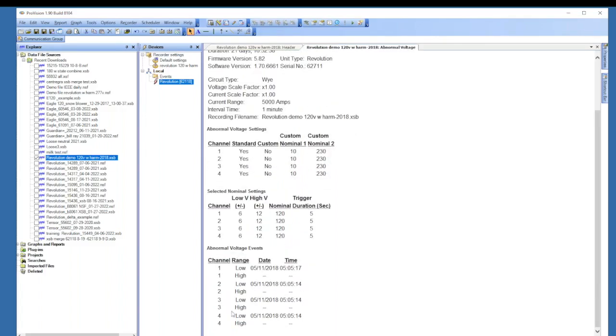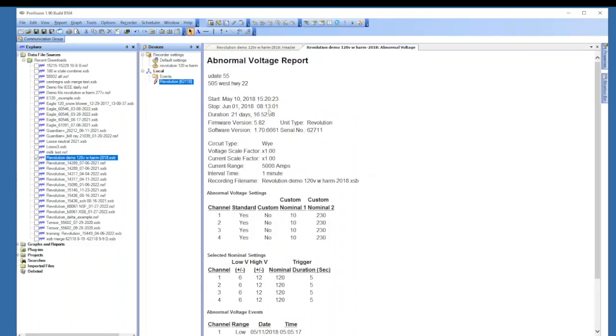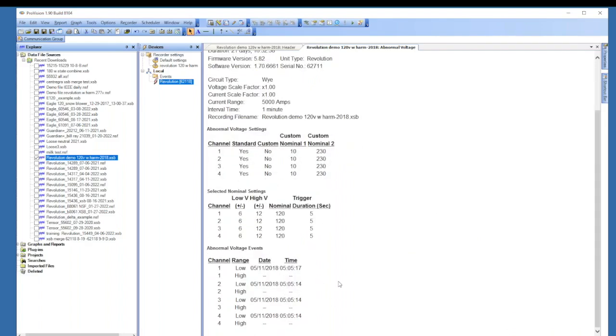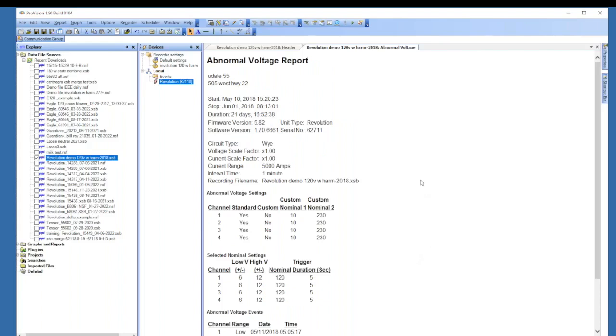Okay, so let's take a look at abnormal voltage here. Just clicking on this, you'll just see that it tells you whether or not you broke out of the low range. The reports do tell you what those settings are. So here we have a plus or minus 6 and a plus or minus 12. So on these dates, we just broke out of the low range. Now you do have to look and see if your start and stop times coincide with any of these events, because you can, again, bounce the voltages when you're installing the recorder. So you can just disregard any of those.